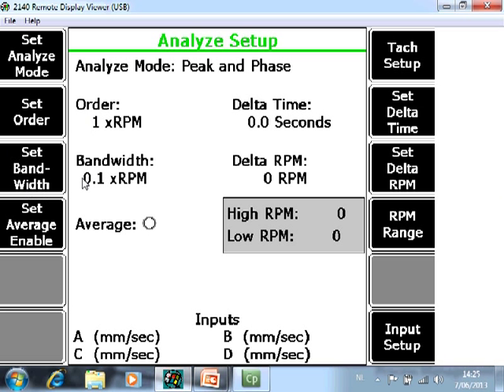F3 Set Bandwidth is default setting 0.1 RPM. That means you will measure a bandwidth of 10% around the imbalance value and that is a recommended setting.